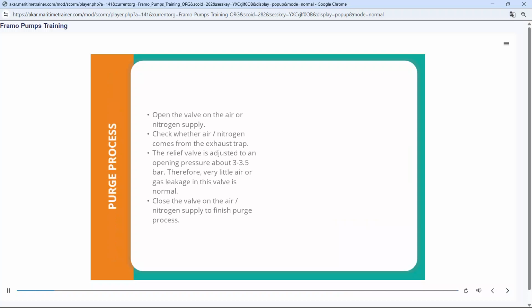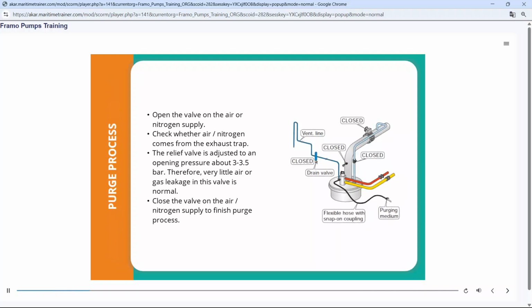Open the valve on the air or nitrogen supply. Check whether air or nitrogen comes from the exhaust trap. The relief valve is adjusted to an opening pressure of about 3 to 3.5 bar. Therefore, very little air or gas leakage in this valve is normal. Close the valve on the air or nitrogen supply to finish the purge process.